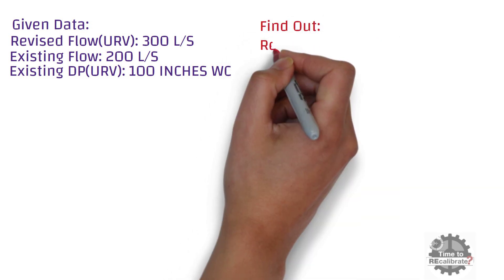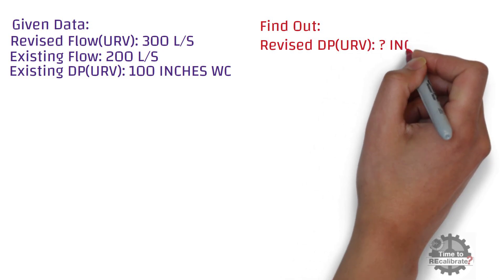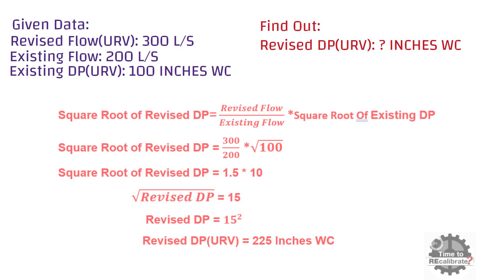From these given data, we need to calculate the revised upper range value of differential pressure — in other words, the new upper range value of differential pressure for the new flow range. Now, put all given values into this standard calculation formula and do the simple math calculation. You will get 225 inches water column of differential pressure.